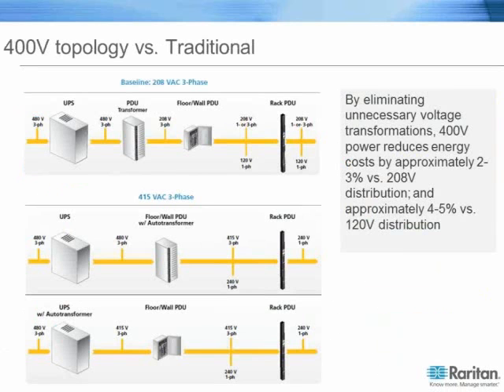So traditionally, we would see utility power coming into a UPS. It would go to an on-the-floor PDU transformer, then to a floor PDU or a row PDU, and then eventually to the rack PDU. Now, there were a couple of bad things here. You had that transformer on the floor. This generated heat. So if we can take a source of heat out of the data center, that's a definite plus. Second of all, we would lose power. Whenever you do a transformation, when you step something down, we're losing efficiency.